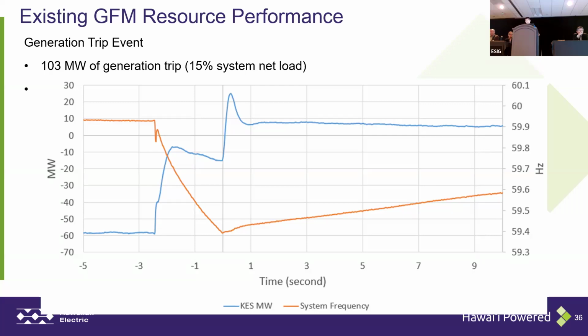Once frequency hits the threshold, which is 59.4 hertz, the FFR module gets triggered, so we see another jump in the megawatt. And then after that, frequency starts to recover, totally turning the direction. So in this roughly 10 seconds of curves, we see first the GFM response, and then FFR together with the GFM response. I believe PFR response also kicked in, but it's blended. I want to say it's blended.